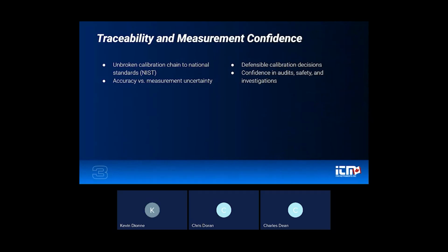Traceability. So this is very important. When we talk about traceability in a technical sense, we're referring to an unbroken calibration chain that's recognized all the way back to a national standard, most commonly NIST. Every reference standard in that chain is calibrated on a defined schedule with documented accuracy and known measurement uncertainty.